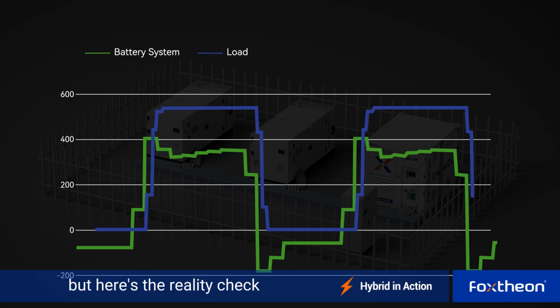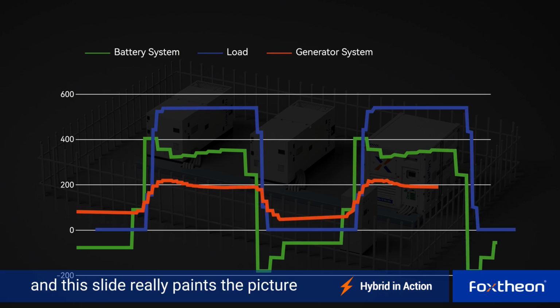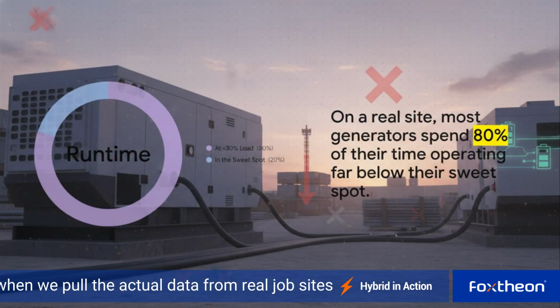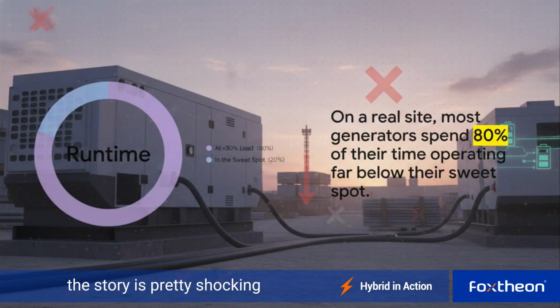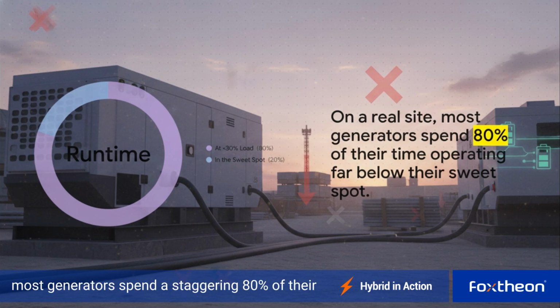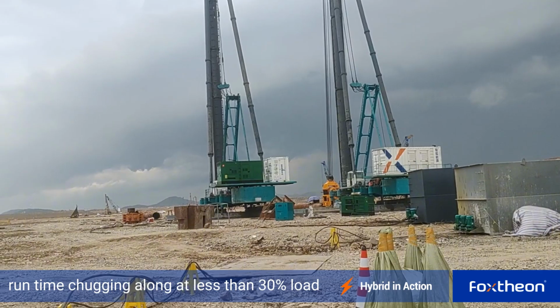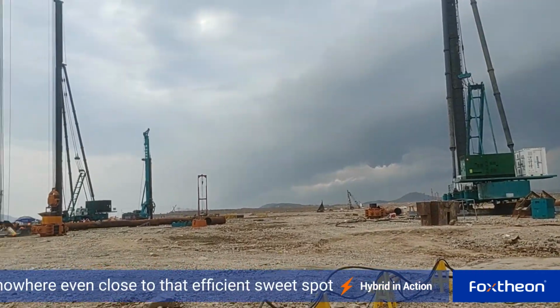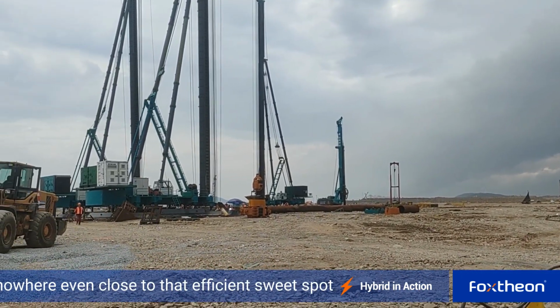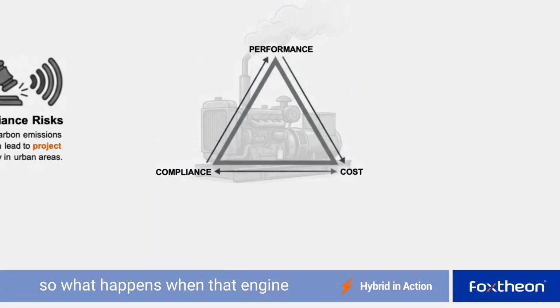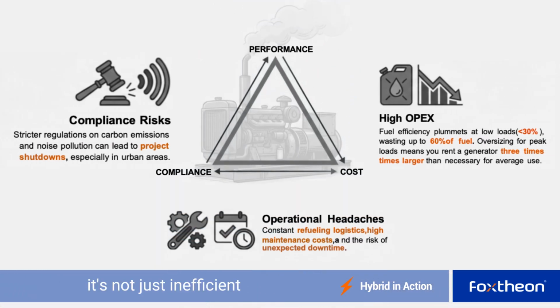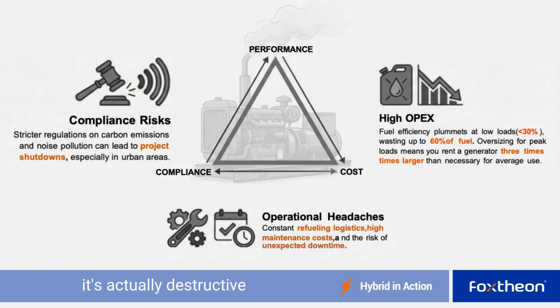But here's the reality check. When we pull actual data from real job sites, the story is shocking. Most generators spend a staggering 80 percent of their runtime chugging along at less than 30 percent load, nowhere close to that efficient sweet spot. So what happens when that engine never hits its ideal pace? It's not just inefficient, it's actually destructive.